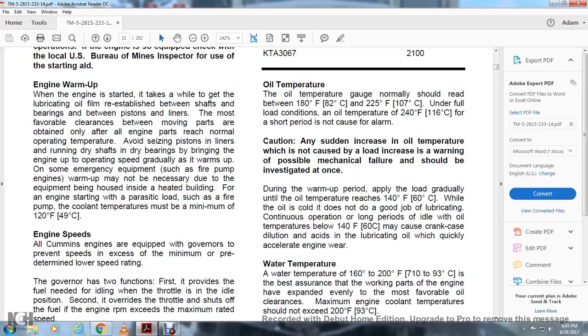During the warm-up period, apply the load gradually until the oil temperature reaches 140 degrees Fahrenheit. While the oil is cold, it does not do a good job of lubricating. Continuous operation with long periods of idle with the oil temperature below 140 degrees Fahrenheit may cause crankcase dilution and acids in the lubricating oil, which quickly accelerate engine wear.